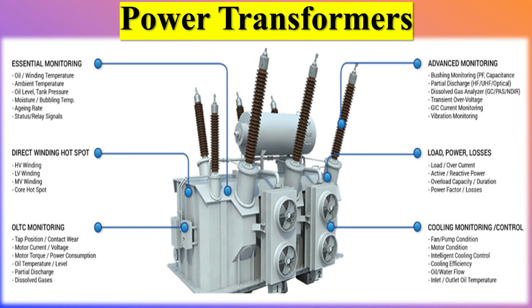The Partial Discharge Monitor Module measures electrical partial discharges (PD) in the transformer, bushing, and, when applicable, the connected ISO phase bus. Electrical PD monitoring is a perfect second-level diagnostic tool to complement DGA and bushing monitoring systems. Advanced analytics: the key analytic for bushing monitoring is the magnitude and trend of the current imbalance, and a DTM can provide system alarms on both of these quantities. Secondary analytics include the behavior of the current imbalance with top oil temperature and the vector of the current imbalance.